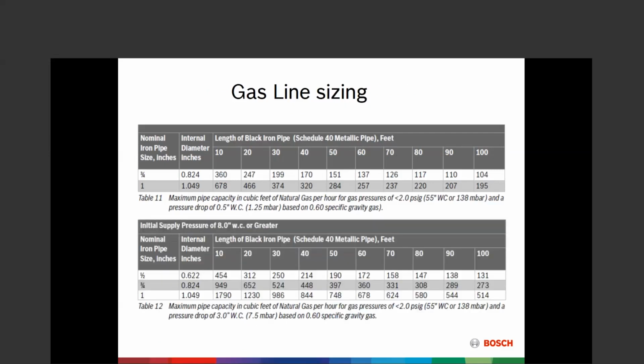And here we go. This 1/2 inch chart now allows for a 3 inch pressure drop, but says that you have to start with at least 8 inches of water column on natural gas to use that 1/2 inch gas line. And you can see on that 1/2 inch gas line, we can get out to 40 feet on 1/2 inch if we have that gas pressure to manage that for us.